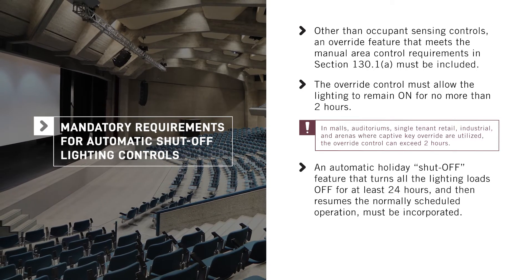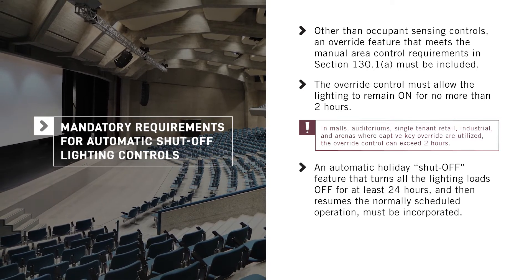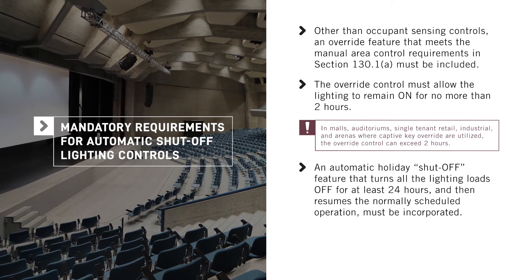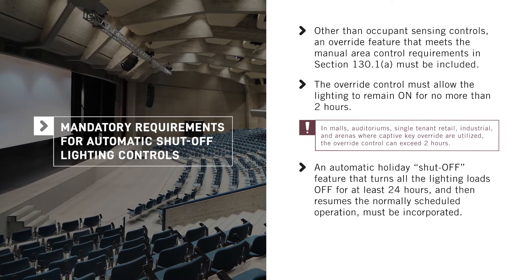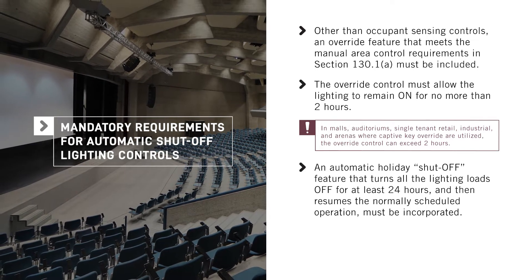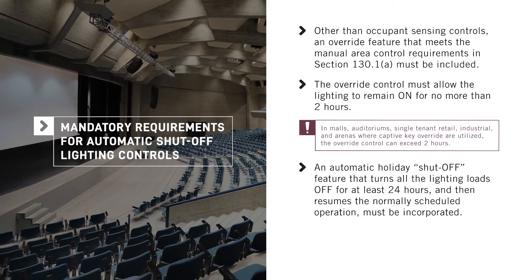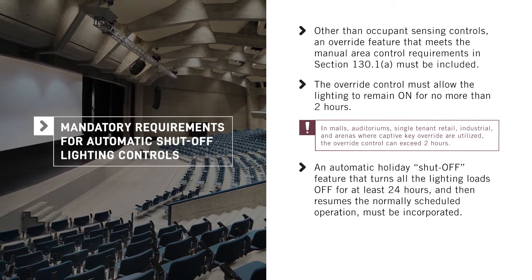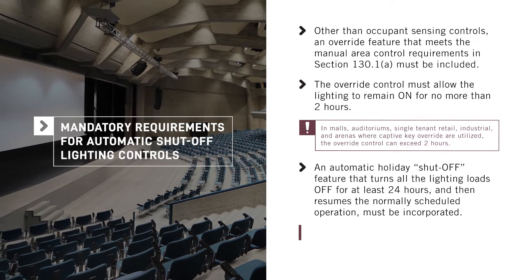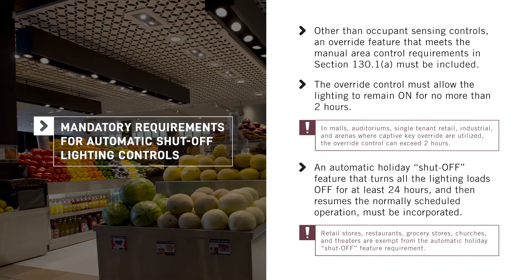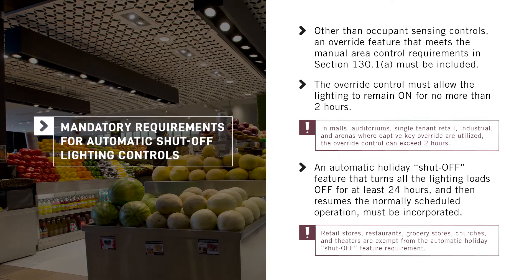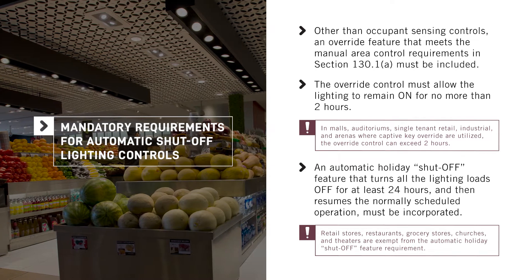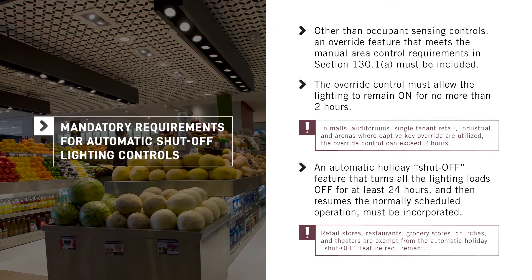Automatic time switch controls must also incorporate an automatic holiday shutoff feature that turns all lighting loads off for at least 24 hours and then resumes the normally scheduled operation. This feature is not required for retail stores, restaurants, grocery stores, churches, and theaters.